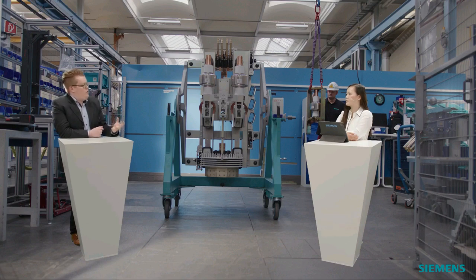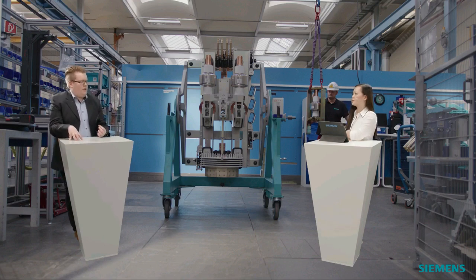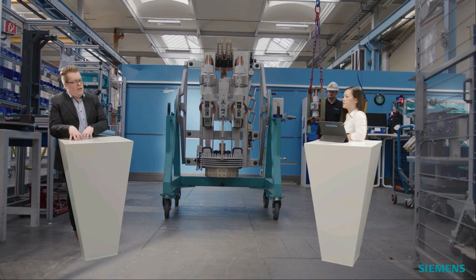Then we also have to differ between a no load operation, where the generator is running at no load without any fault location, and the generator in service. When we calculate the generator in service with the short circuit calculation, we also have to use at least 300 volts if we do not know the specific arc voltage at the fault location. This is also required by the standard.